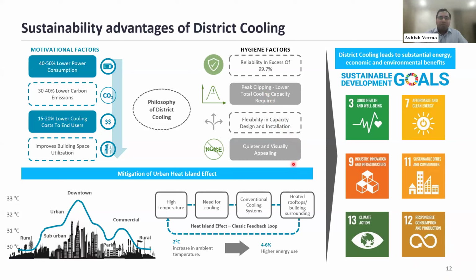in the buildings. A very important feature of district cooling is how to mitigate the urban heat island effect, which is very prominent in our urban centers. If you see the graph on the left hand side, the temperature rises from the rural area, where it is around 30 degrees C, to almost 3 degrees C higher when you go to the downtown. This is the impact of the urban heat island effect, and district cooling can help mitigate this kind of phenomenon, because district cooling plants can be located away from the downtowns in a more remote area.